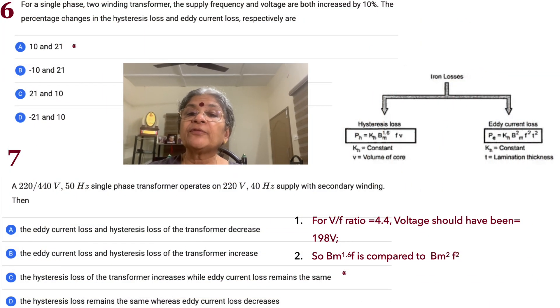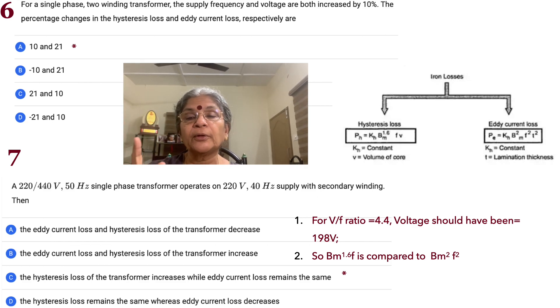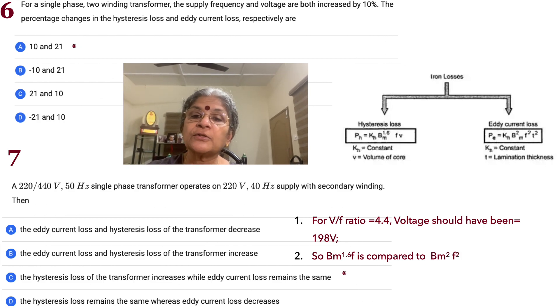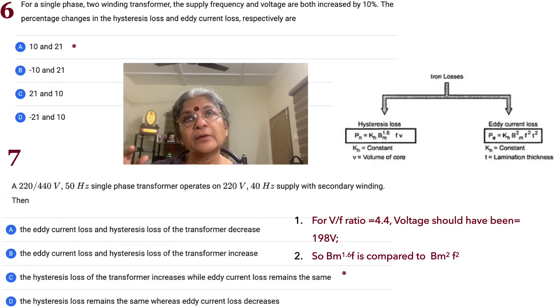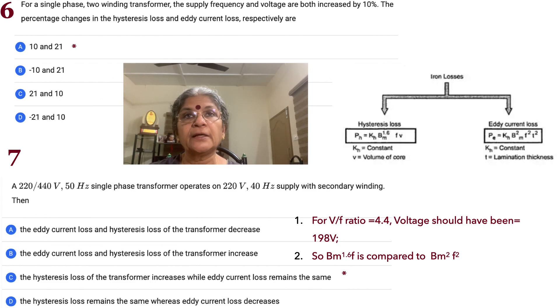Problem 6: for a single-phase two-winding transformer, both supply frequency and voltage are increased by 10%. Since V/f remains the same, flux is unchanged. A 10% increase in frequency gives a 10% increase in hysteresis loss (proportional to f). For eddy current loss, frequency squared gives 1.1² = 1.21, so a 21% increase.